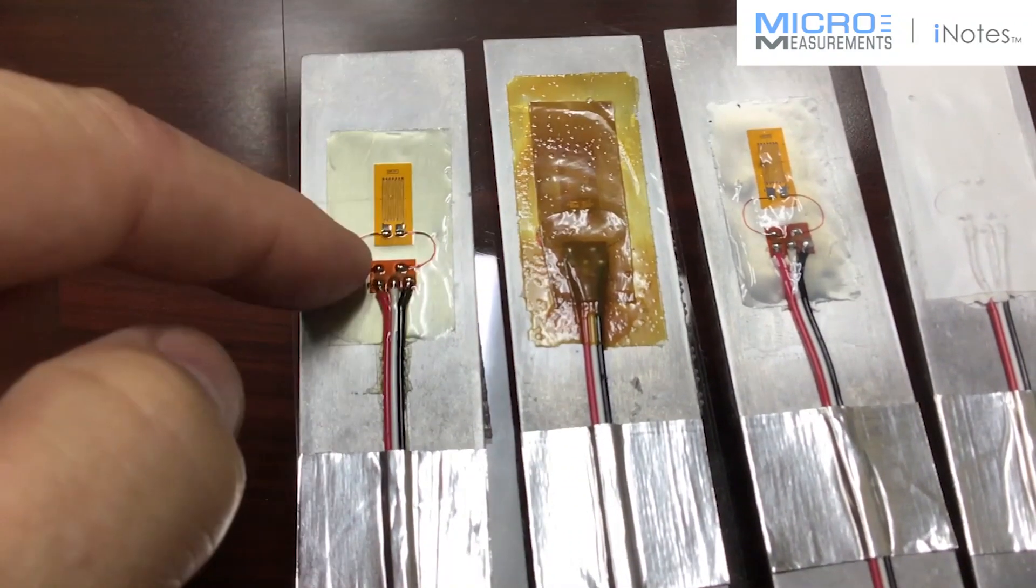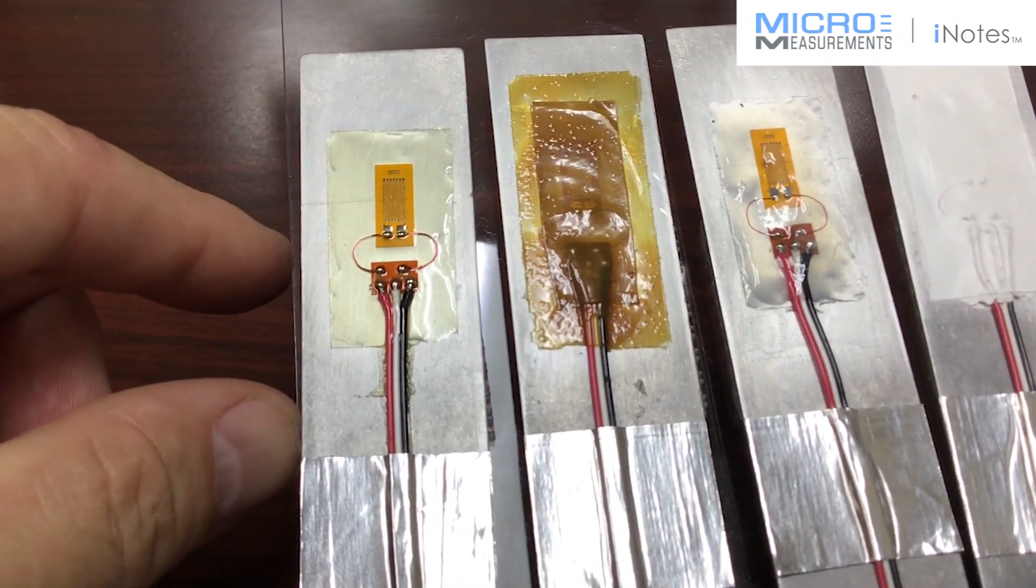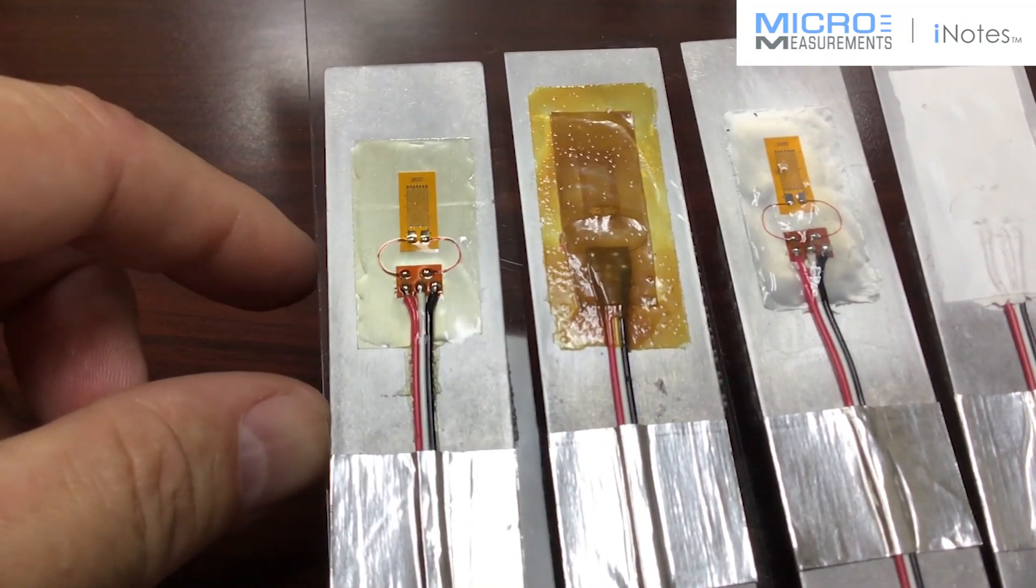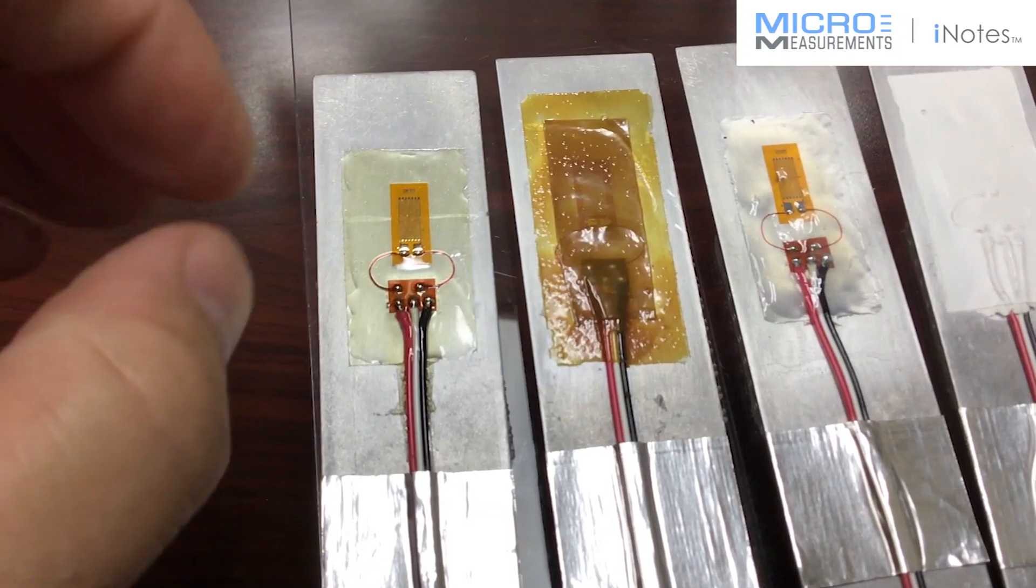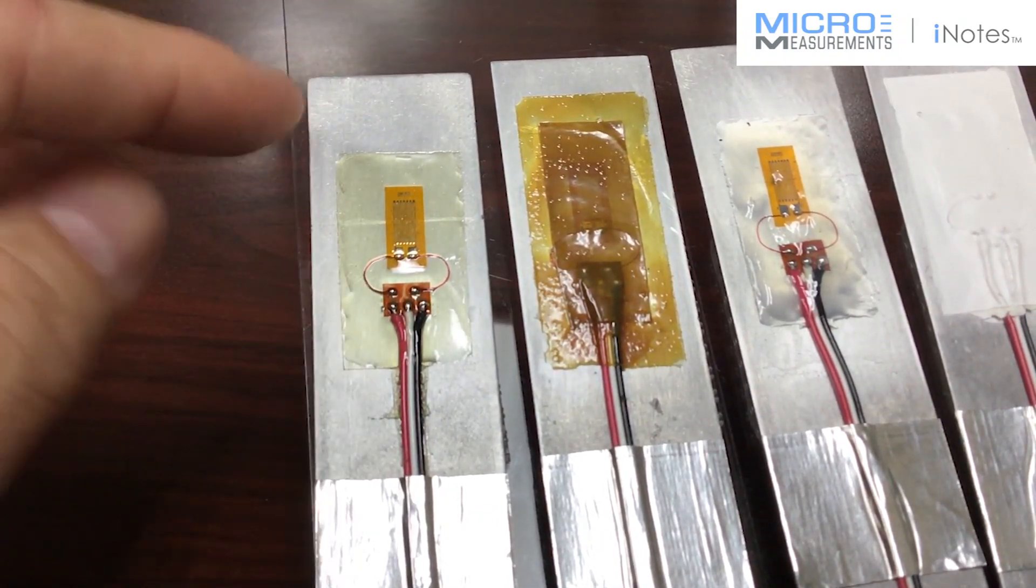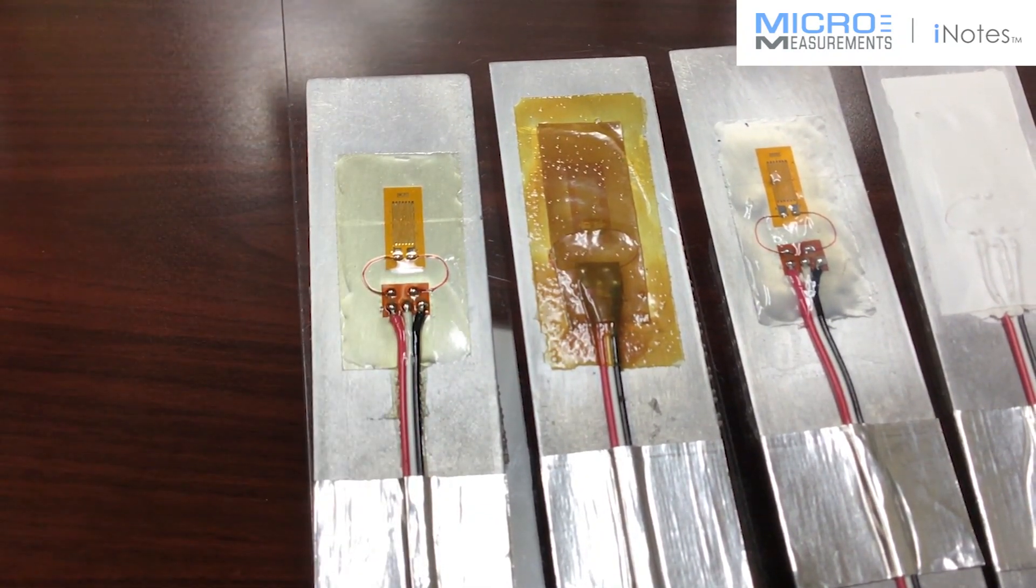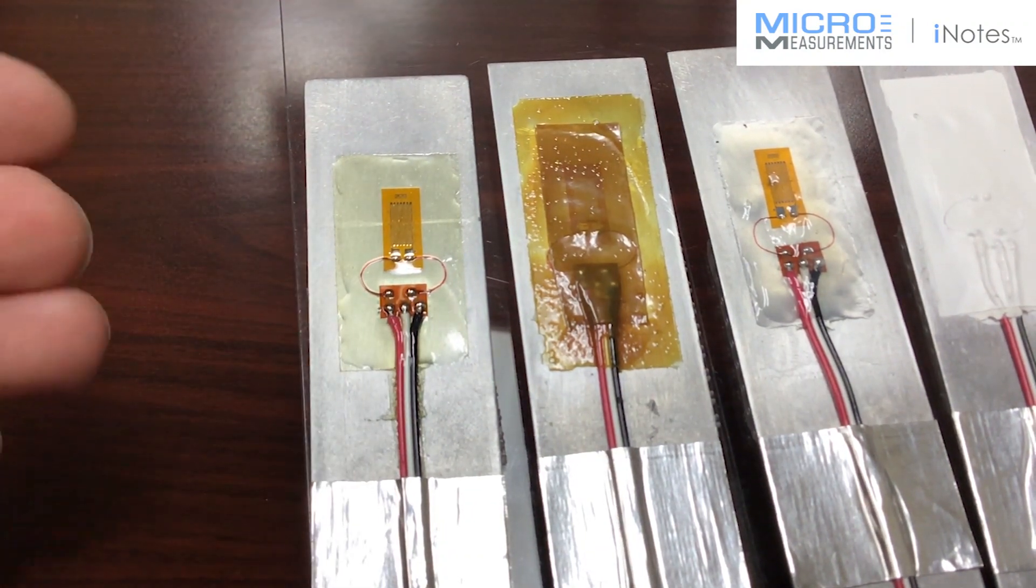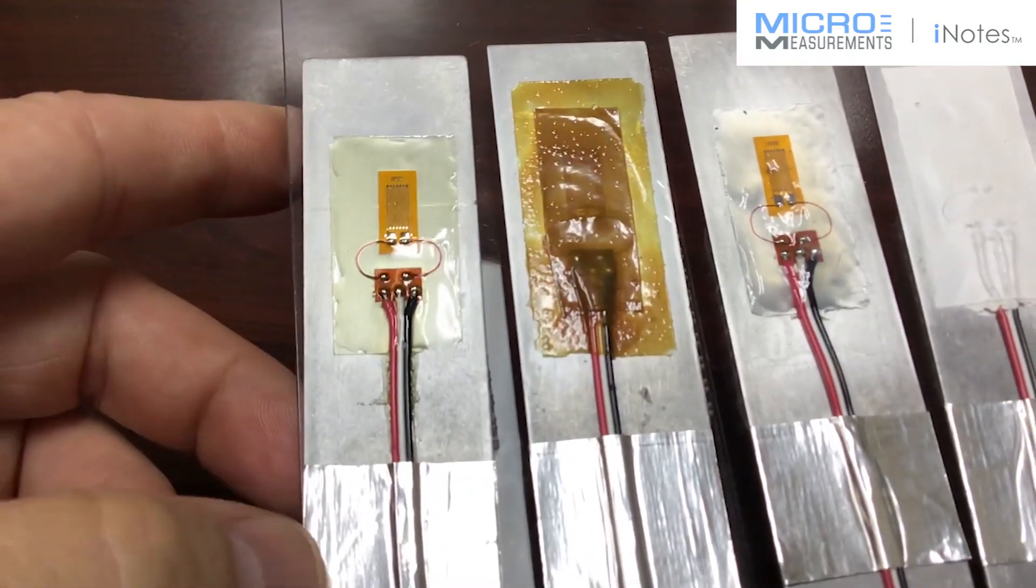It forms a thin hard layer over top the gauges. It's about like the conformal coatings that they put over top of printed circuit boards. It's a thin layer that's good for laboratory type environments, but if you have a more adverse environment you probably ought to consider going to something else.